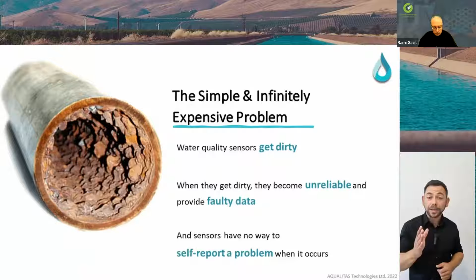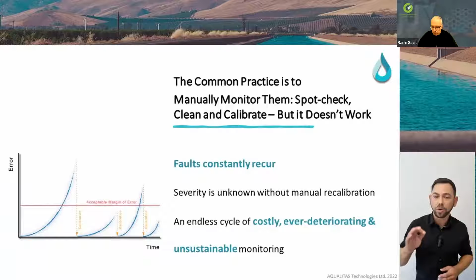Look here, for example. The moment the sensor goes into water, the error starts to grow until the next maintenance event. But as the operator never knows what the error at each time is, they do not trust the data collected by their sensors. So they go back to do manual tests, eventually acting based on their experience and their hunch.